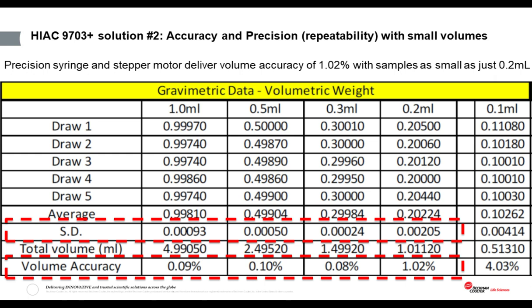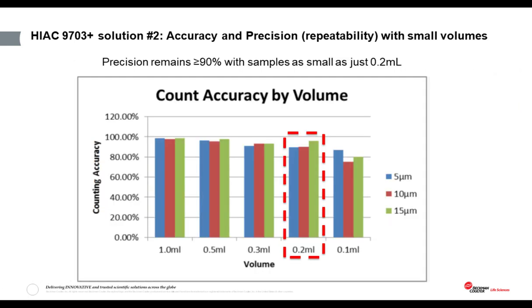And thirdly, the precision syringe and stepper motor drive maintains repeat volume accuracy and precision on samples as small as 0.2 milliliter, which is the smallest sample volume USP 787 says we can use. And as can be seen in this table, testing on the sample accuracy of the HIAC 9703 Plus proves that the accuracy on samples as small as 0.2 milliliter is just plus or minus 1.02%. And the precision calculation gives us a standard deviation of just 0.00205 on these samples.